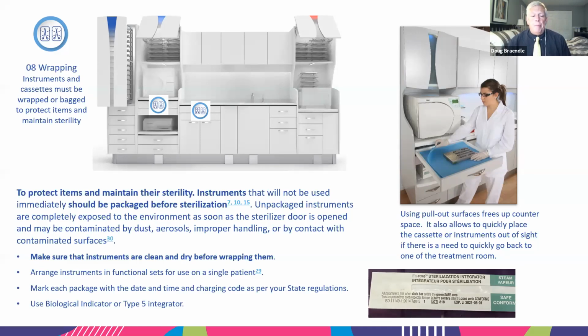Here's what I recommend. There are things called type 5 integrators, and it's like a strip. Actually, there's one on the right-hand side there, down on the bottom of the page. Some of them have green, others have blue. It's a kind of a waxy substance. And if you look on the back of these things, it looks like a thermometer. What happens is it does multiple parameters. It checks for time, it checks for temperature, it checks for steam. It checks basically almost everything that you're going to need to prove that you've had a successful sterilization cycle.